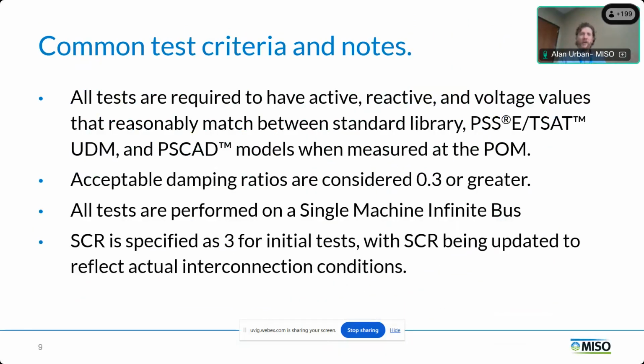All right, I'm going to start going into the actual tests we run. There are not that many, so we can cover all of them in this presentation, and you'll see exactly what we're looking for. Some common test criteria and a few notes here. All these tests are required to be benchmarked. Every model is required to be benchmarked against each other so that we can see how different the standard library model might be from the UDMs and from the PSCAD models. All these measurements are taken at the point of measurement, which is the high side of the generator step-up transformer. That is our reference point of applicability.